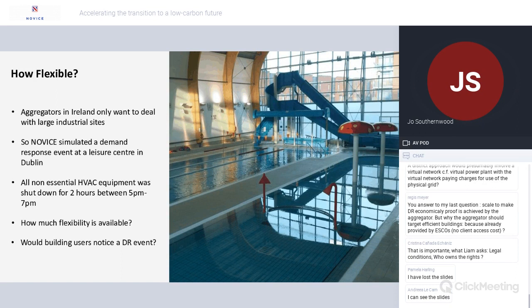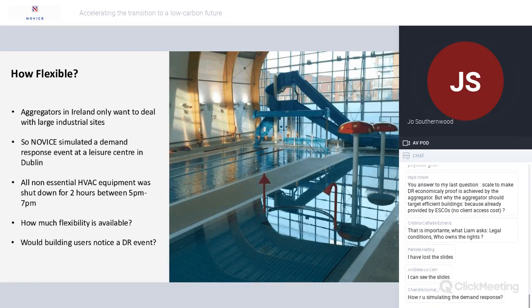So what we did was simulate a demand response event at this leisure centre. We identified all the non-essential HVAC equipment and shut it down for 2 hours between 5 and 7 p.m.—the busiest time for a leisure centre on a typical weekday. We wanted to find out how much flexibility is available from this building, and whether the building users would notice the impact of this demand response event.